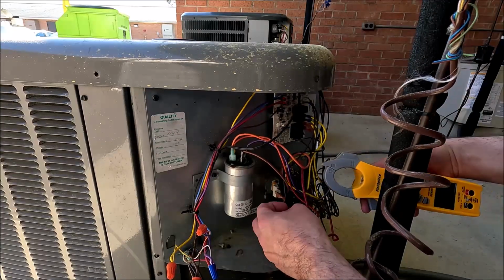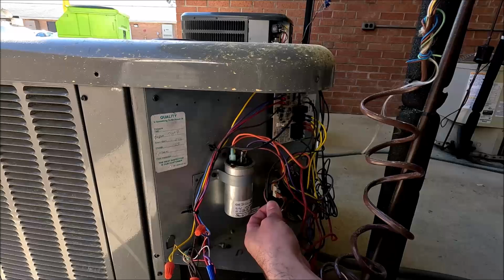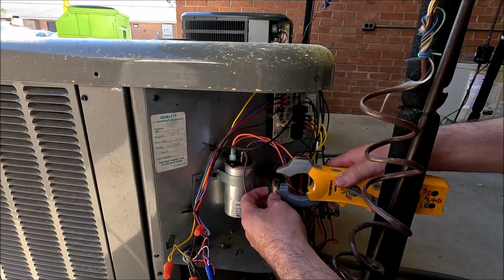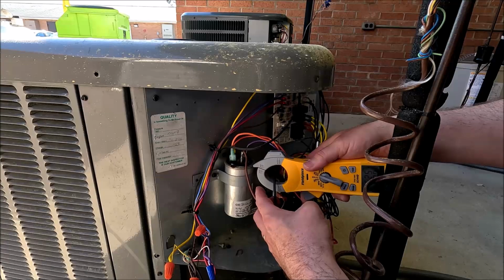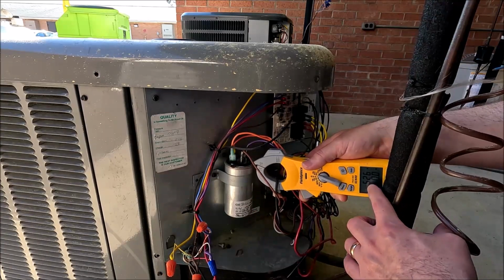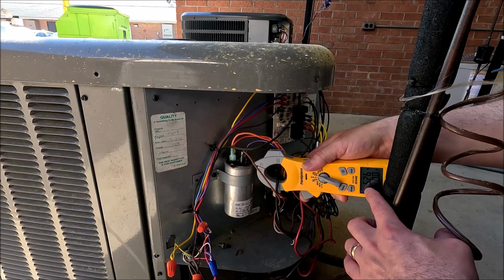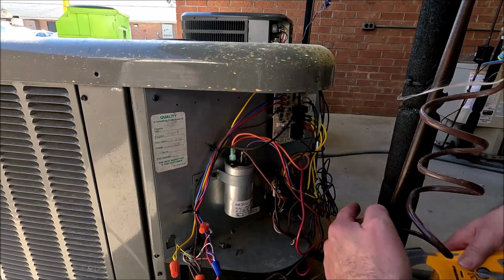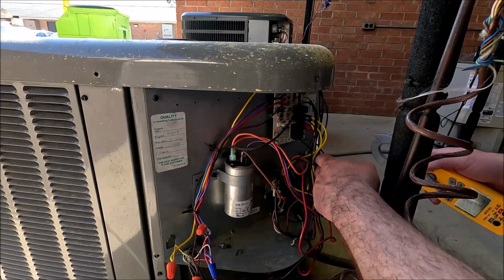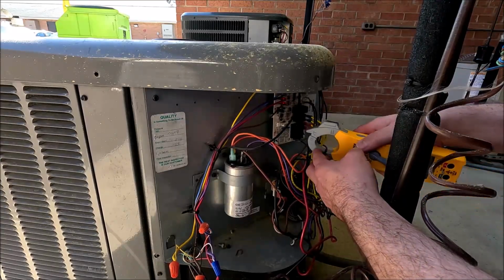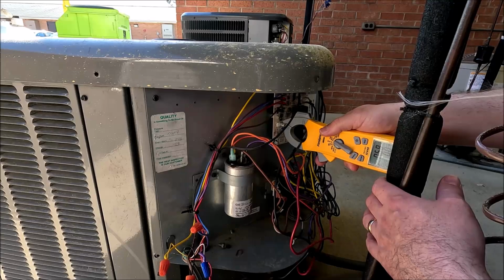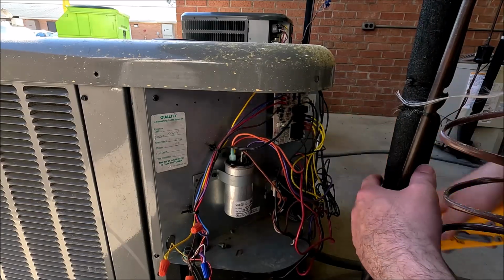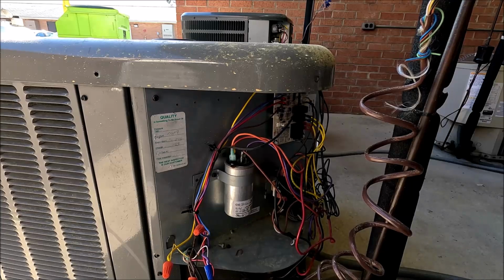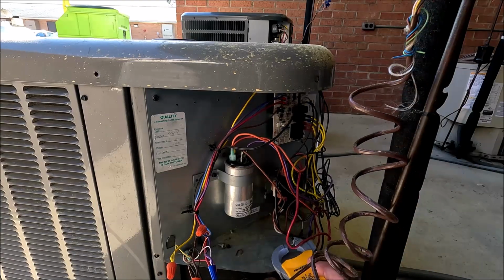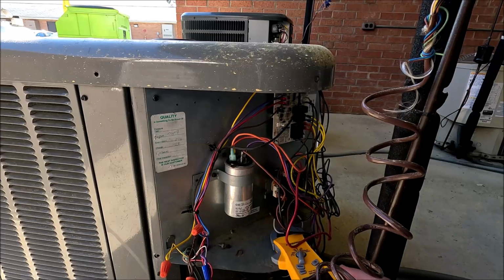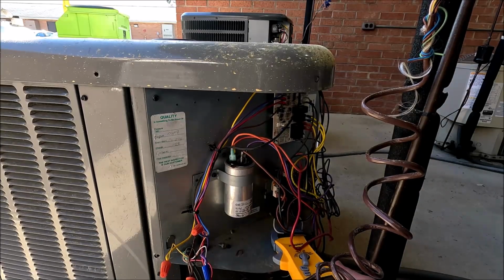And whoever did this made a mess. They got wires twisted off. We'll fix that later. But, well, that's actually the compressor, not the outdoor fan. So I've got 5.25 amps on that compressor. And here, right here on the defrost board, that's going to be my outdoor fan, and it's pulling 0.58, 0.59. So if I did the bottom, the line side of the contactor, I would get 6 point something amps, right at 5.8.